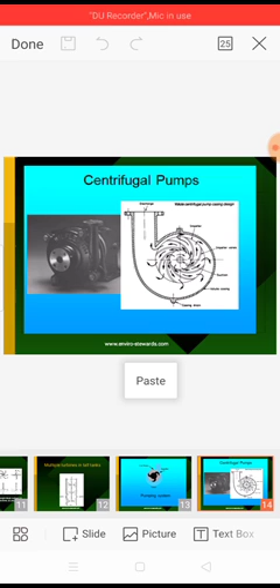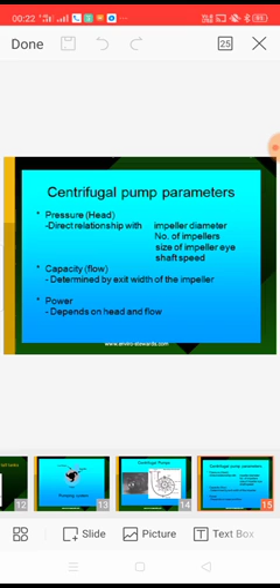Pressure has a direct relationship with impeller diameter, number of impellers, size of impeller eye, and shaft speed. The capacity or flow is determined by the exit width of the impeller, and the power depends on the head and the flow.